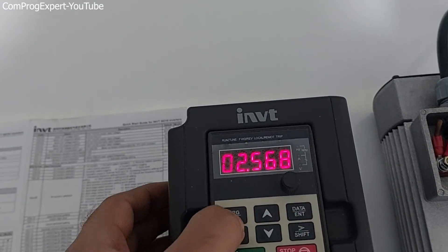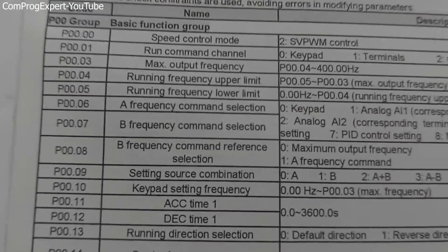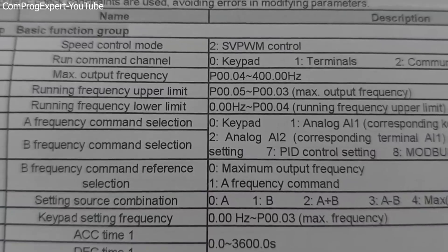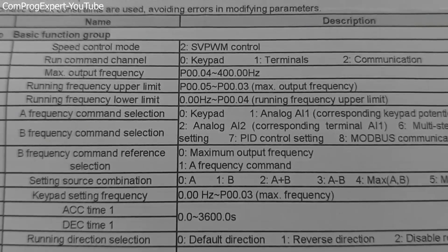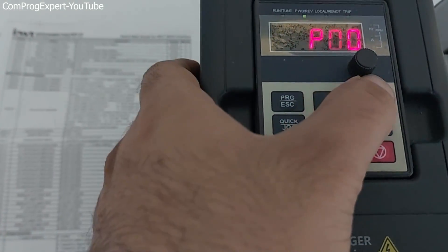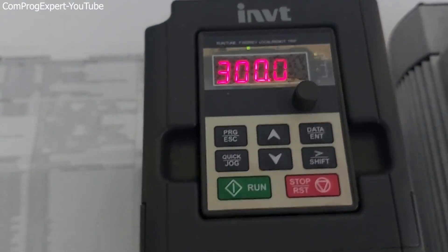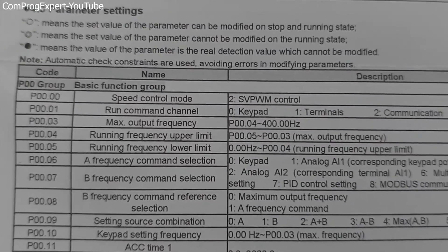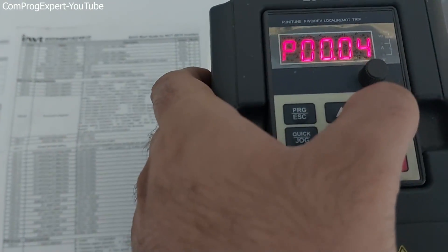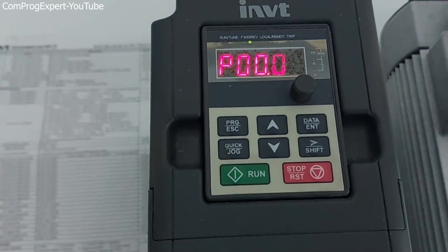Consider that the rated frequency of the motor should be lower than the maximum frequency. Here we have two parameters: the maximum output frequency and the running frequency upper limit. P00.03 is the maximum output frequency and we should set the limit. These two values are both set equal to 300 hertz.